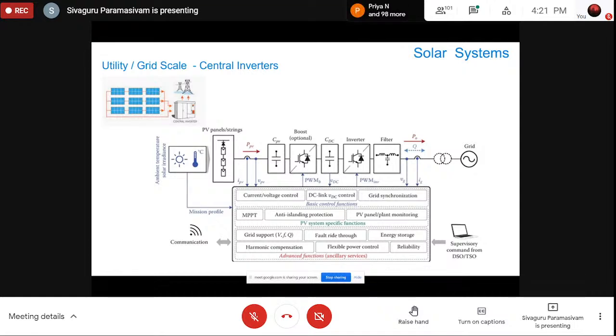Directly, the sun's irradiation is directly proportional to the output current from the PV module, but the voltage is always in the control of the inverter, because we can switch and we can alter that. So the voltage is changed, and then the power will be tried to be kept at the maximum at all points of time. So that's the reason we call that maximum power point tracking. That's an algorithm.